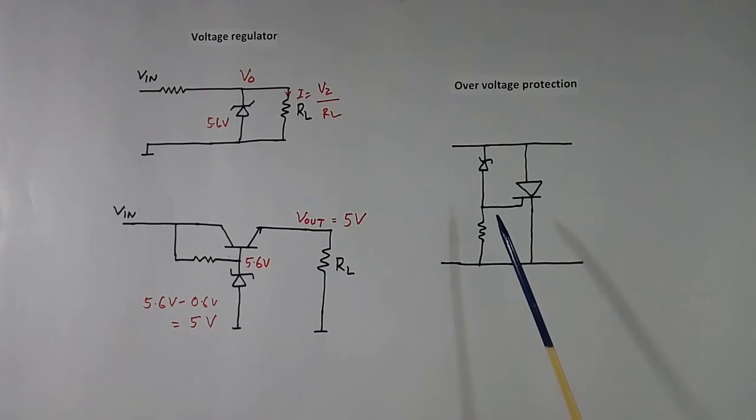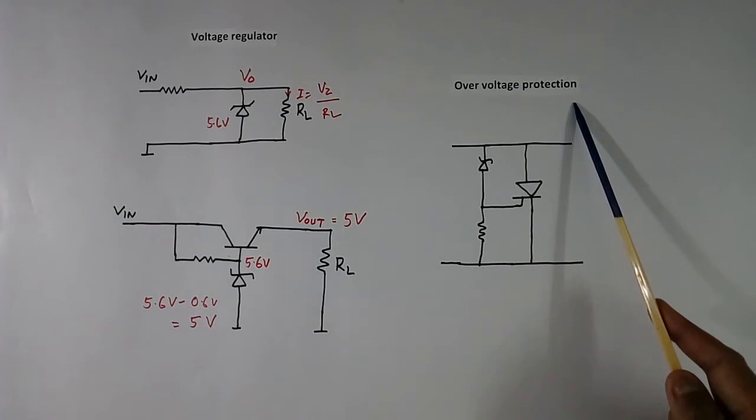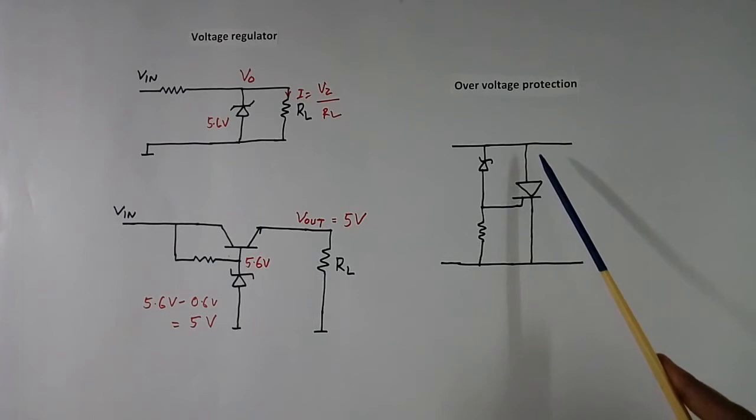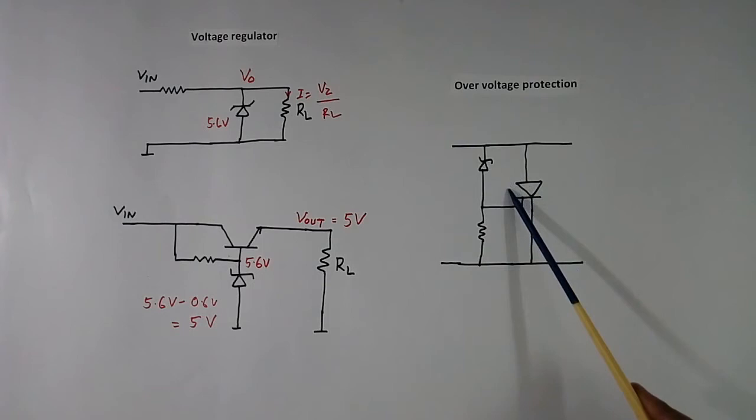Now this is another application of Zener diode in over voltage protection. This is thyristor. I have connected one Zener diode in gate. This resistor is connected to suppress noise. When voltage across this becomes equal or more than the Zener diode, the Zener diode will conduct and the gate current will flow like this. Because of this gate current, the thyristor will trigger and this will become short. It will not be fully short because there will be drop of thyristor, small drop. Now current will flow like this.